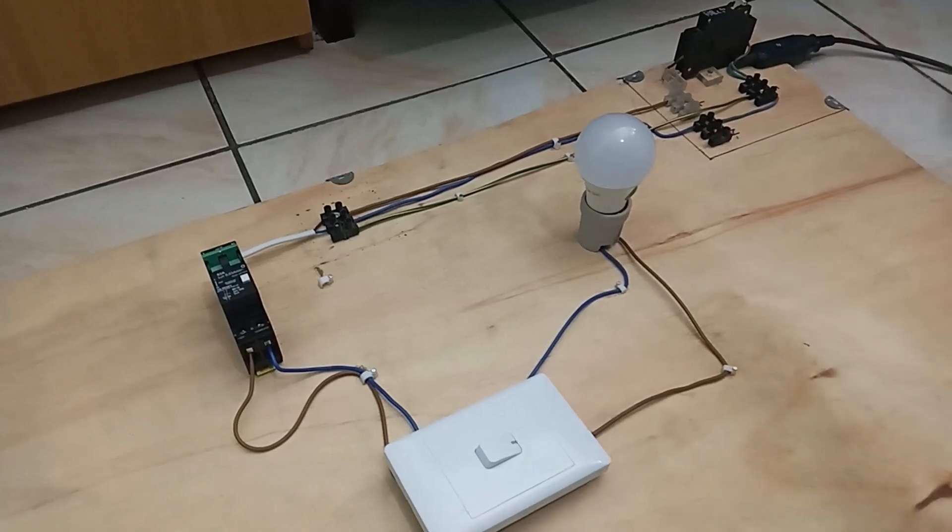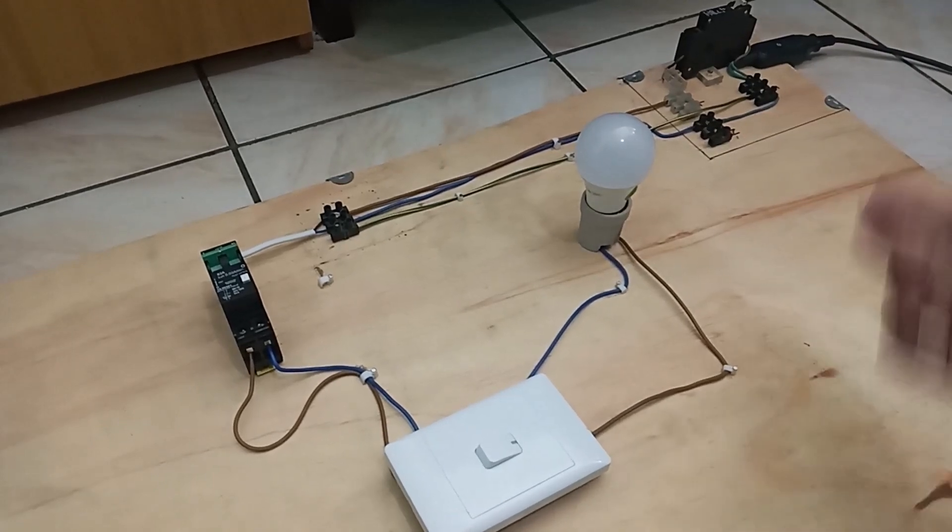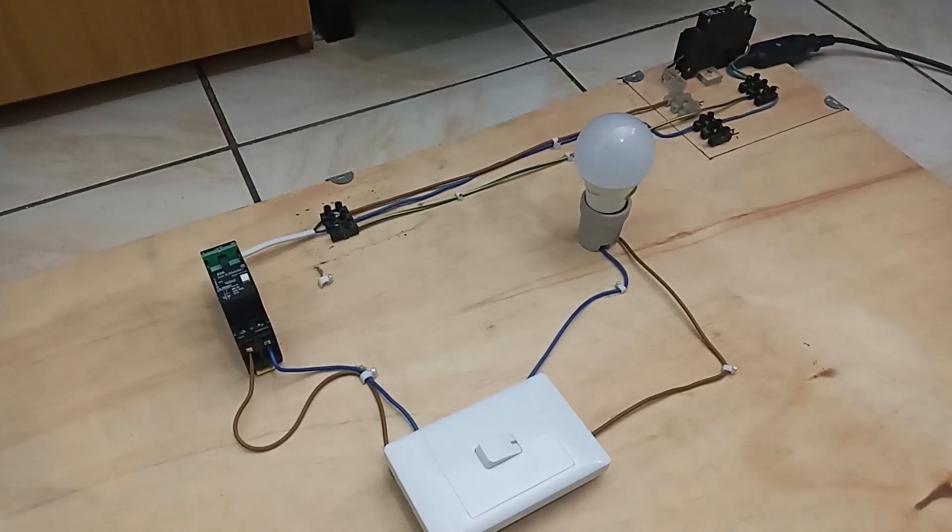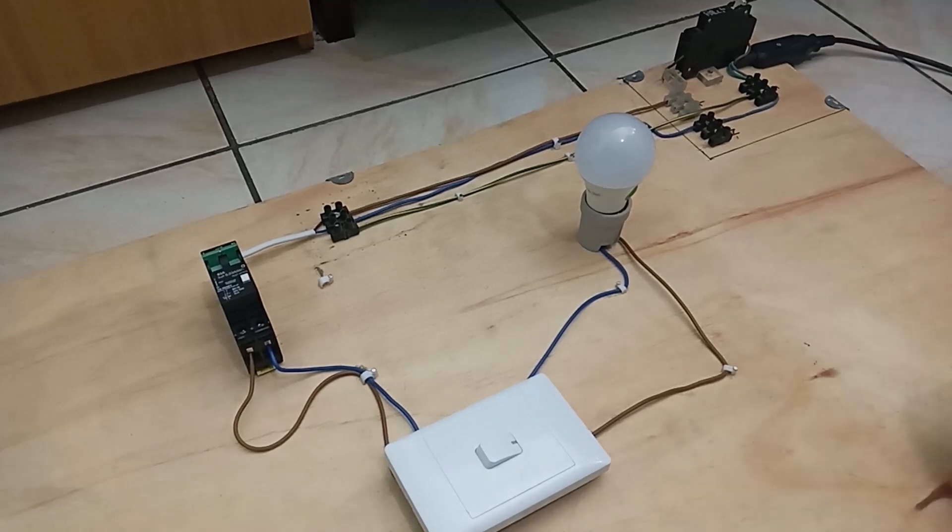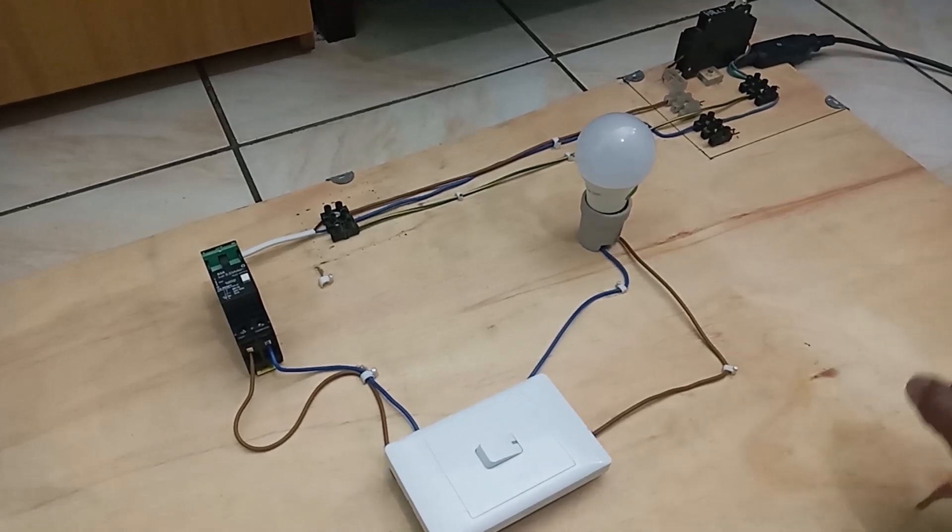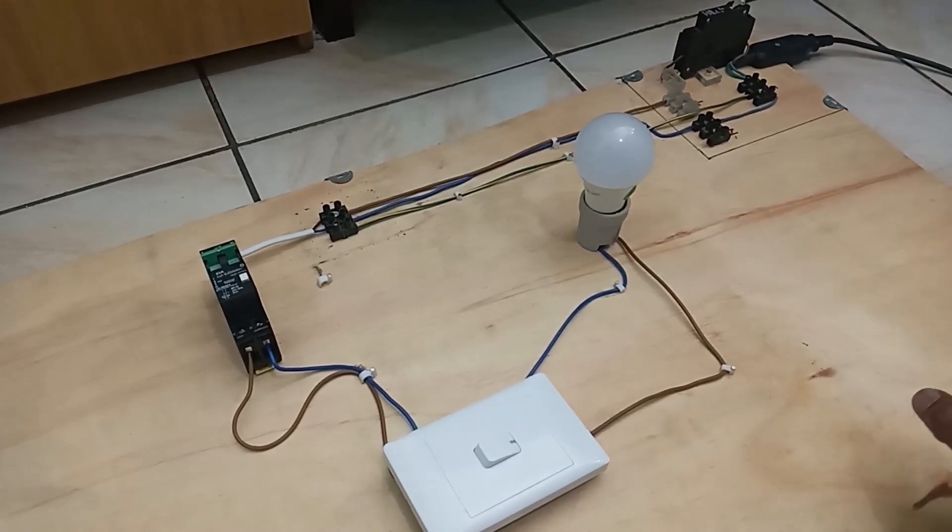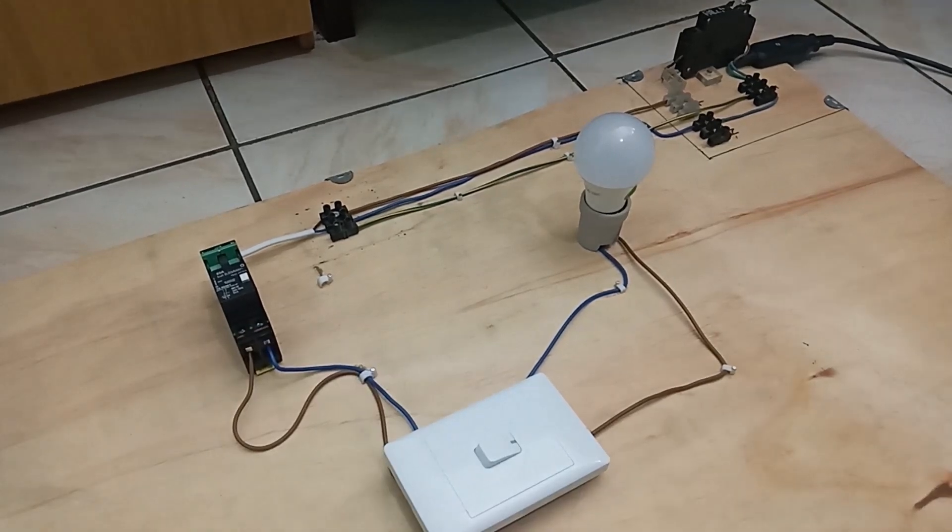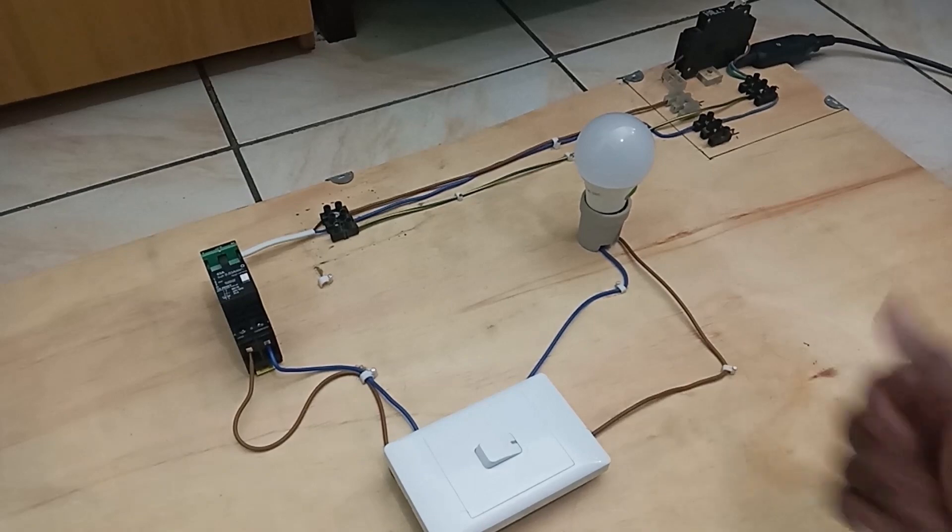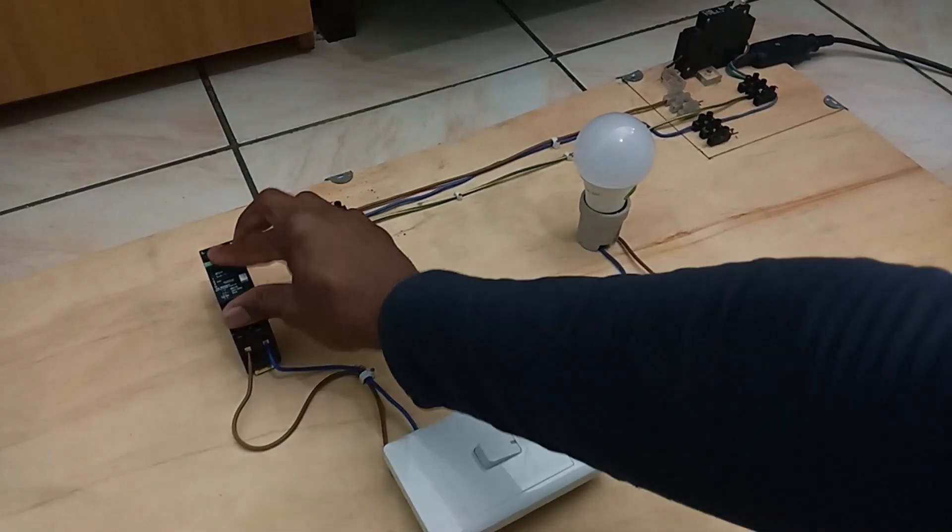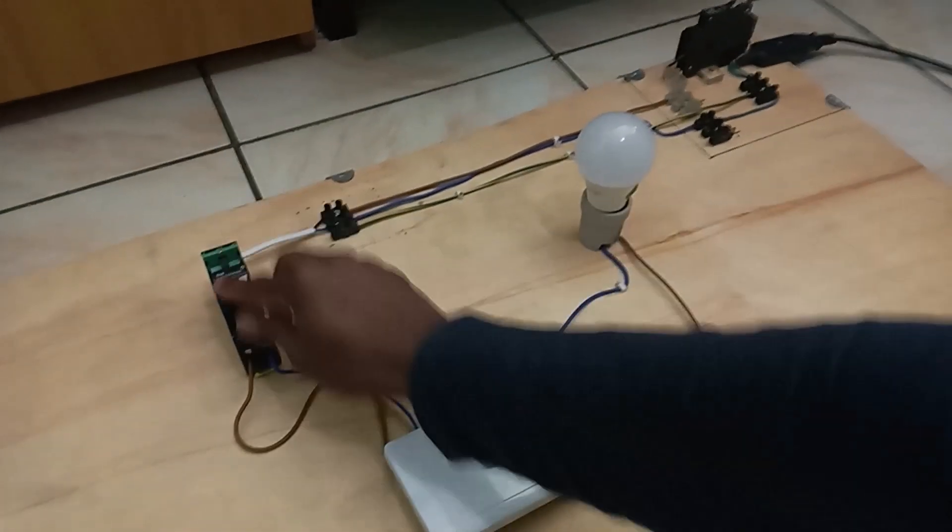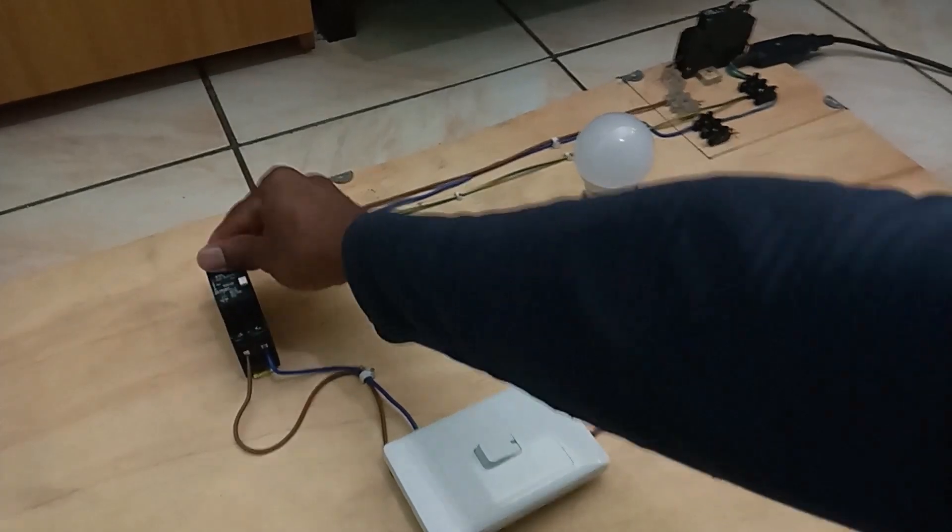So if you connect an equipment that going to draw more than 20 amps, then this breaker must trip to say, I was not rated for that amount of current. So I will trip to protect everything. And this one here will only trip for small current greater than 30 milliamps to protect yourself. So this is basically how it operates.